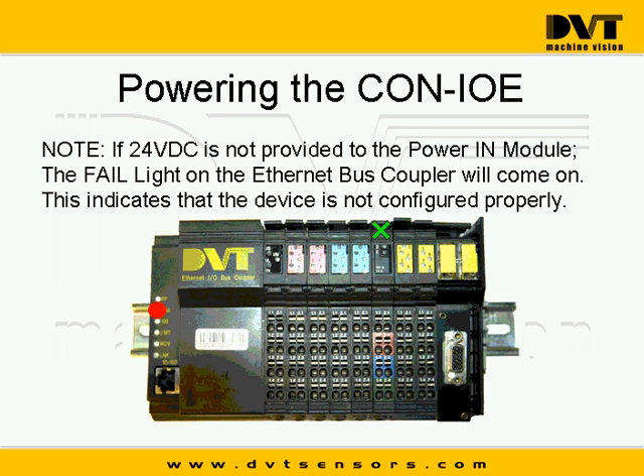So a lot of times what folks run into is that they'll supply a network connection over to the far left. They'll supply power everywhere they need to supply power here to the bus coupler and all of the input and output modules on the Ethernet I/O modules, but they won't supply power to the breakout board side, and the camera won't be getting power. And a lot of people assume that because they're right next to each other, one of these power connections will power the entire thing. Well, if you throw this power in module here, it completely separates that power backplane from the rest of the DVT IO module here. So even though they're linked up, they are acting as separate power backplanes there.